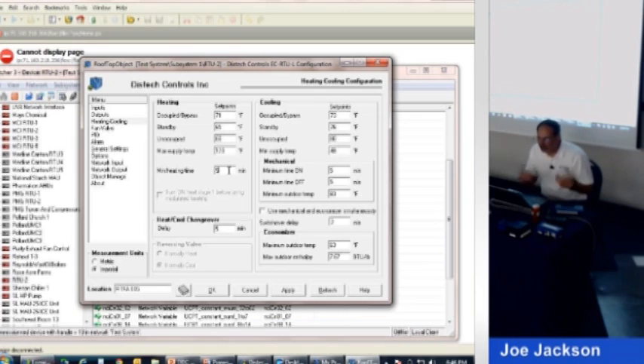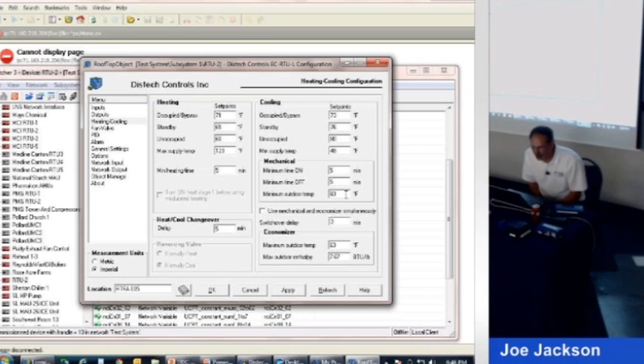Minimum time in heating. If we go into heating mode, we're gonna stay in the heating mode for 5 minutes. Mechanical. Here's a minimum on-off times for your compressors, and here's a minimum outside air temperature for your mechanical cooling. So we're going to let the mechanical cooling run to 55 degrees if it wants to. If it ever gets colder than that, even if the economizer can't keep up, we're going to lock the compressors out. You could drop that as low as you want. It's not a big deal.